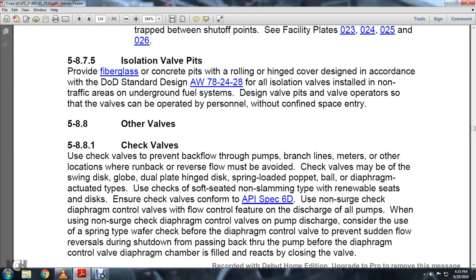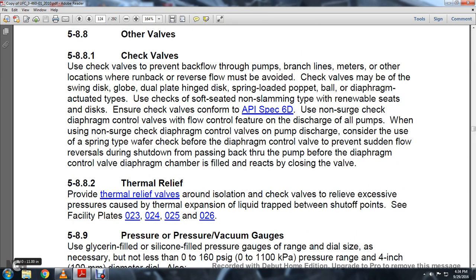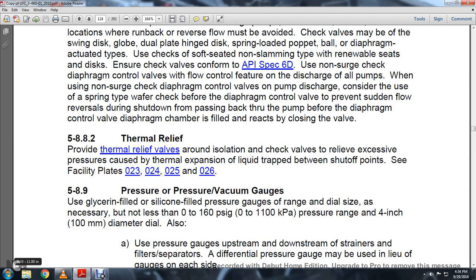Section 5.8.8.1 Check Valves: Use check valves to prevent backflow through bypass pumps, branch lines, meters, and other locations where reverse flow must be avoided. Check valves may be swing disc, globe, double-plate, hinged disk, spring-loaded poppet, ball, or diaphragm-actuated type. Non-slamming type with renewable seat and disk; check valves conforming to API Spec 6D. For non-surge check diaphragm-controlled valves used for flow control at pump discharge, consider the use of a spring-type wafer check valve before the diaphragm-controlled valve to prevent sudden flow reversal during shutdown.